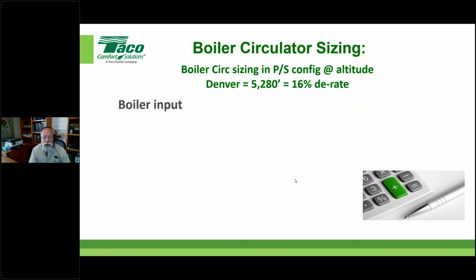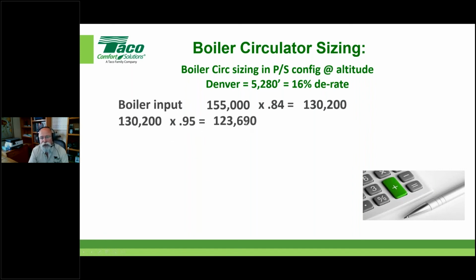Here's one with altitude. Some people say, well, altitude. Again, if you get something from the manufacturer, you go through the steps of proving that you're getting a certain amount of BTUs per cubic foot of gas, then by all means. But like I said, if you get something from the people that supply that gas that say, hey, you're going to take a derate, then be sure to derate that first. Your derate comes off of that. Then that 155 becomes a 130-200, and then you take your efficiency off of it, which gives you a maximum net output. And that's what you size the pump on.